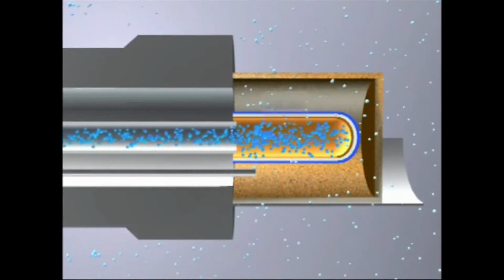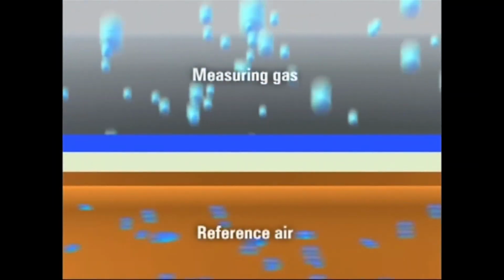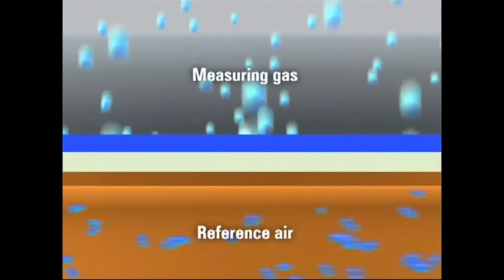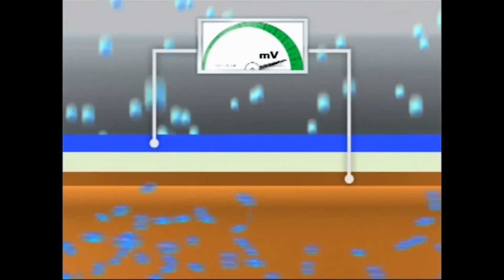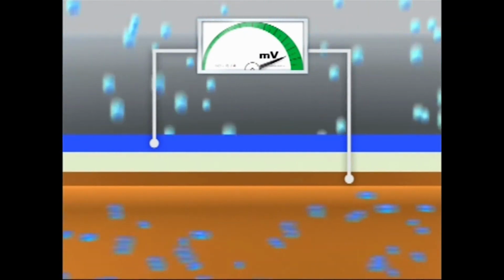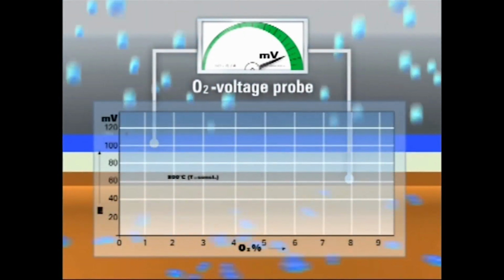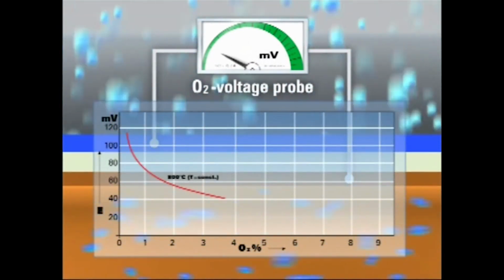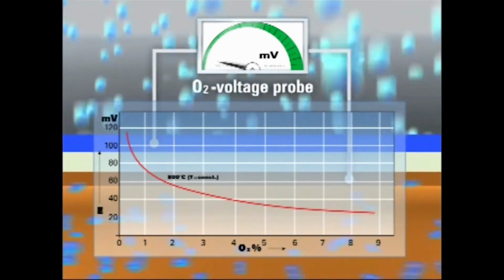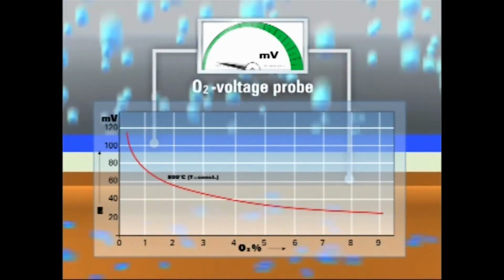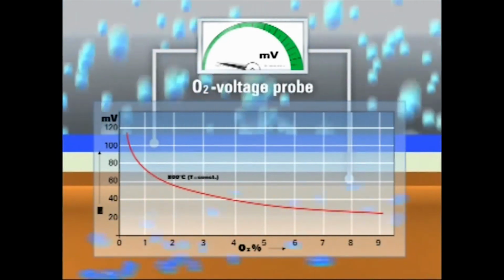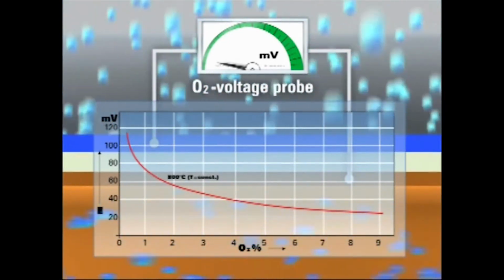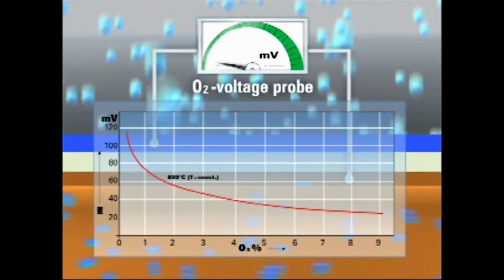As a function of the oxygen concentration, a voltage is generated between the measurement and reference electrodes. This voltage has a logarithmic relationship to the oxygen partial pressure and depends on the temperature of the measurement cell, necessitating the additional monitoring and control of the measurement cell temperature. The calibration of the voltage probe has to be carried out with air and additional test gases due to the logarithmic characteristic line. This results in increased servicing costs.